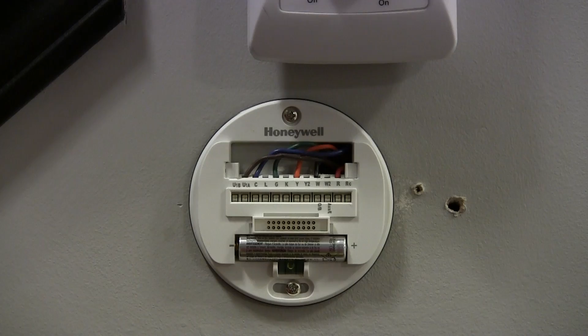I mentioned earlier that there are little side switches that expose or cover up terminals on the thermostat base that we may or may not use. After going through some documentation on the Lyric app, it's worth mentioning that if we're not using the RC or U1B terminals, we should flip these little switches out to cover those terminals. These are actually dip switches that tell this particular thermostat what mode it can or cannot operate in. So as an added precaution, since we're not using these two terminals, we flip this dip switch out to cover the terminal contacts.